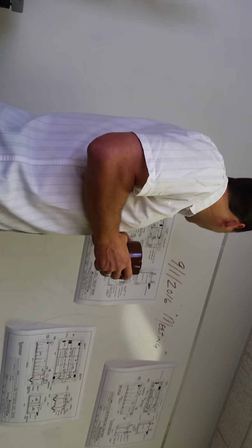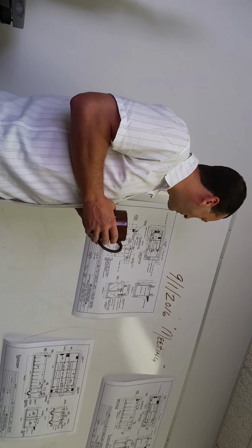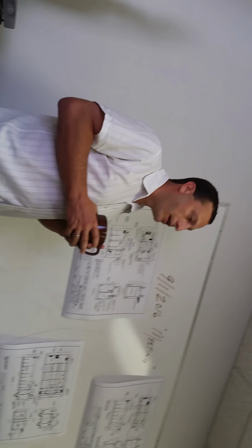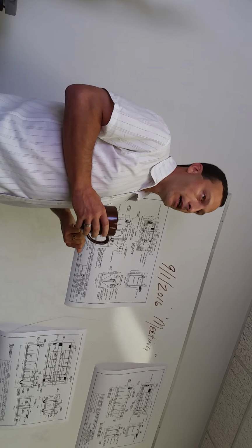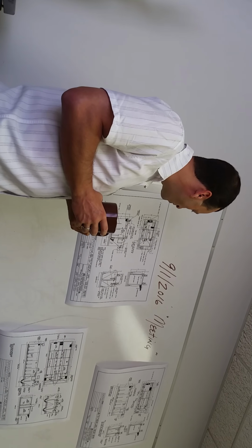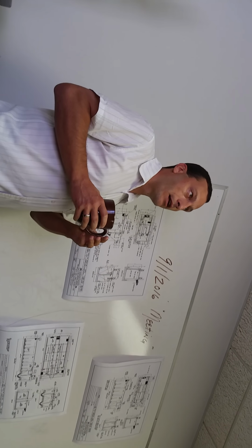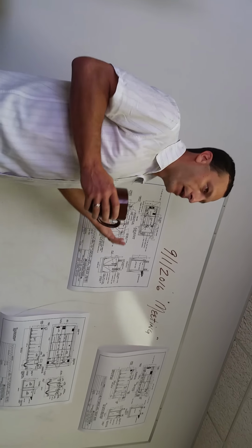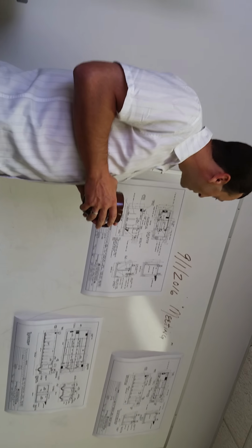Extended aeration. The pros, sort of like I went through, it's a very easy system to operate. It's technology that's been around for quite some time, works fine for secondary treatment. Some of the cons are it's not set up for biological nutrient removal. You're not going to get phosphorus removal, you're not going to get denitrification. So in a lot of the coastal areas where the effluent requirements are going lower and lower and lower, it's just not a viable option anymore. And that's about it.